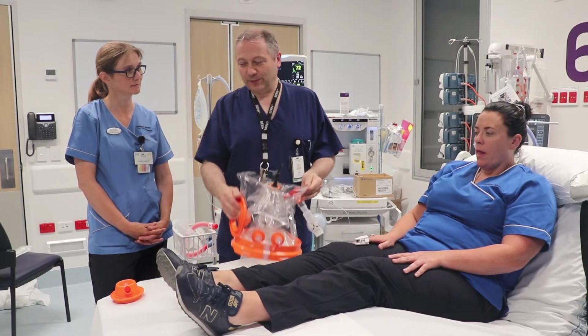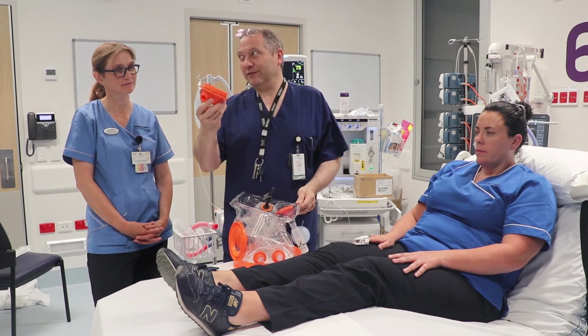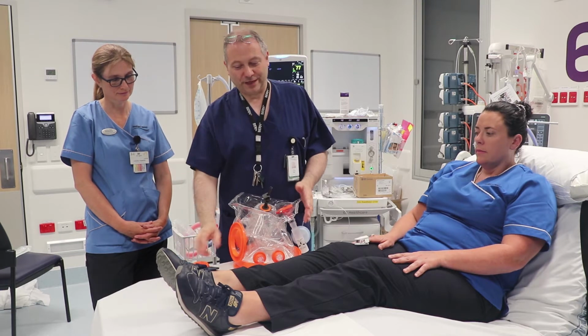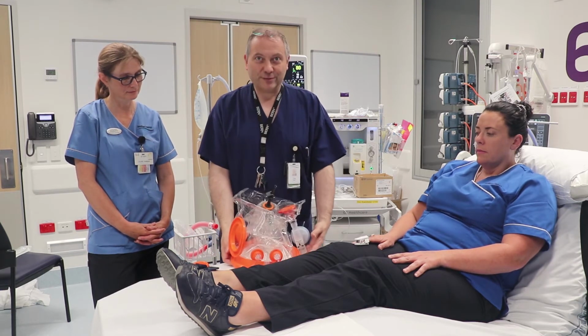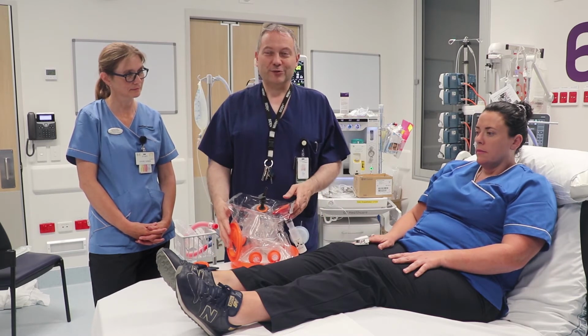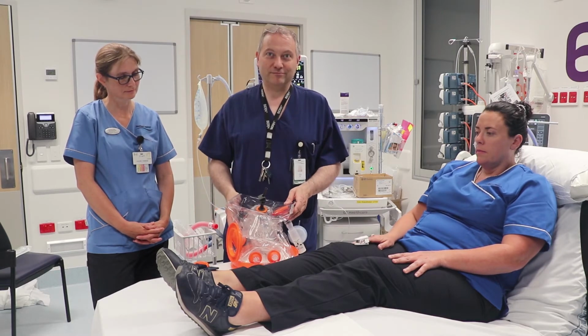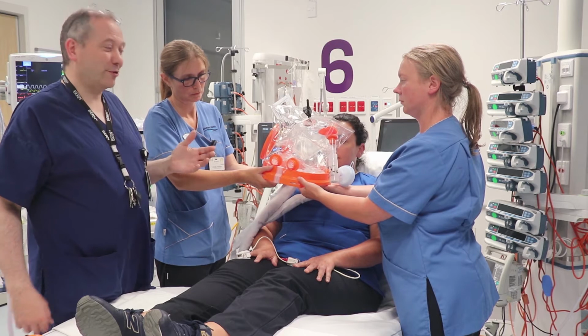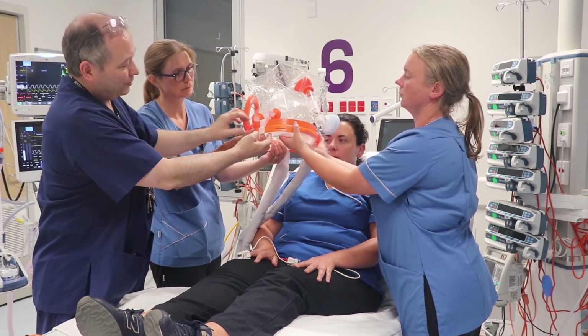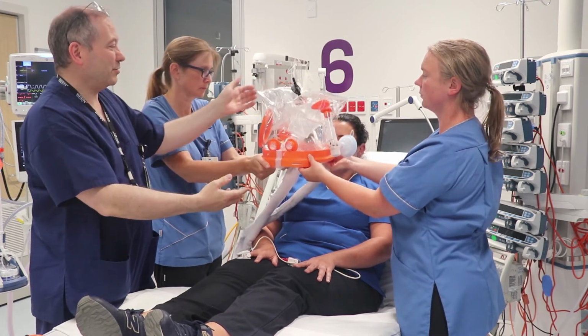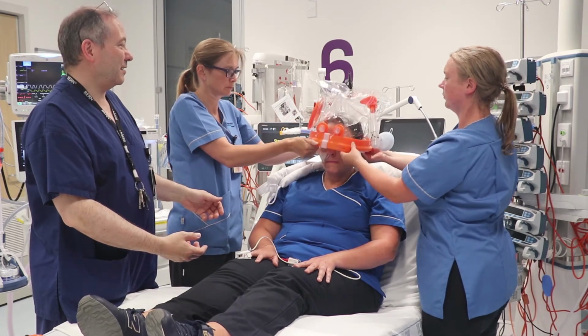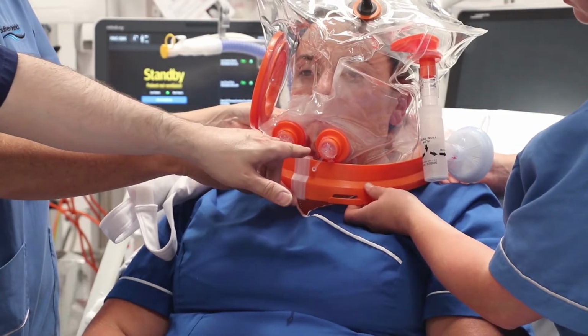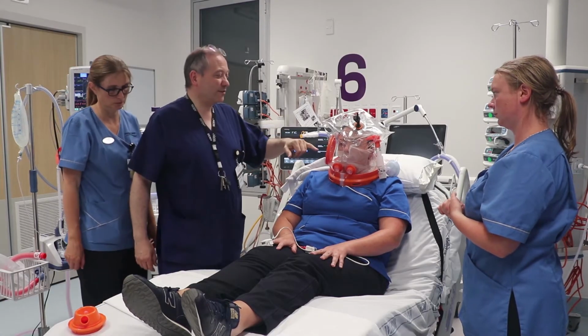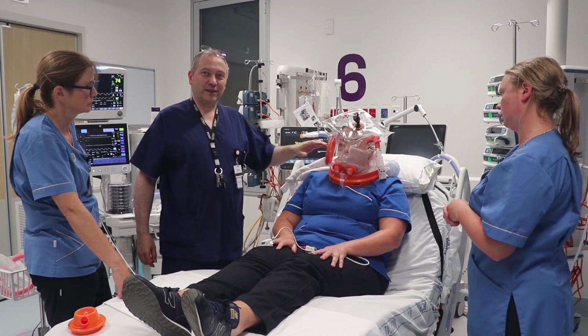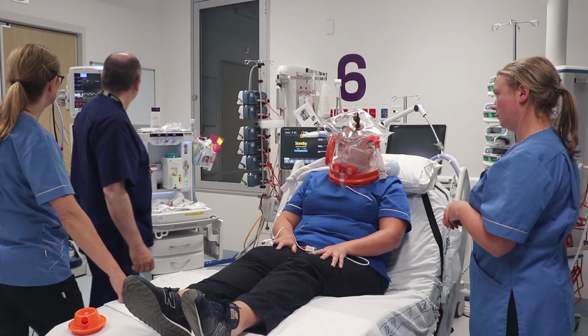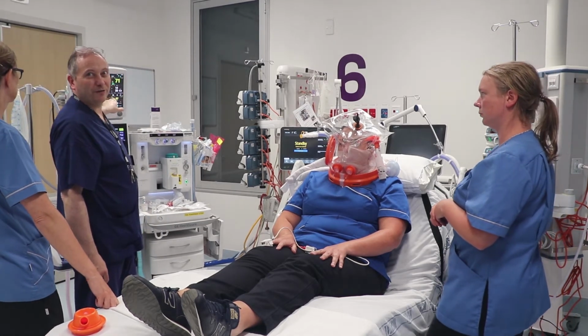So prior to putting the helmet on the patient, we usually remove the free breathe valve. This just makes it easier for the applicants to put the helmet on the patient, and it also makes it safer for the patient to breathe until such times as we've connected the gas inflow. So next, Sarah and Louise are going to put the helmet on Carla. And what they do is they pull the soft collar to the hard collar, and they're going to lift and place the helmet onto Carla, making sure that the two ports are at the front of the helmet. So at the moment, Carla's very safe because the free breathe valve has been removed and the helmet is open to air. And we can see here that despite that, she is rebreathing a little bit of carbon dioxide.